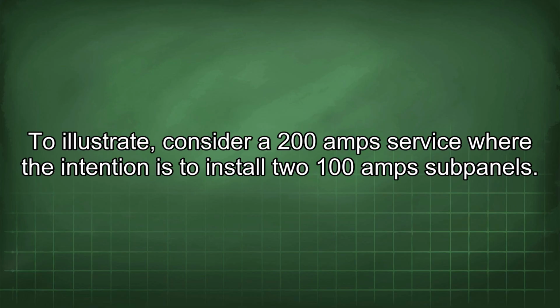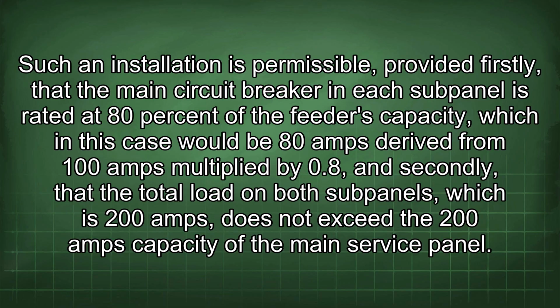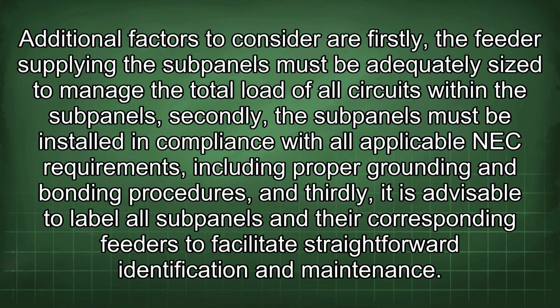To illustrate, consider a 200 amp service where the intention is to install two 100 amp subpanels. Such an installation is permissible, provided firstly, that the main circuit breaker in each subpanel is rated at 80% of the feeder's capacity, which in this case would be 80 amps, derived from 100 amps multiplied by 0.8, and secondly, that the total load on both subpanels, which is 200 amps, does not exceed the 200 amps capacity of the main service panel. Additional factors to consider are, firstly, the feeder supplying the subpanels must be adequately sized to manage the total load of all circuits within the subpanels.